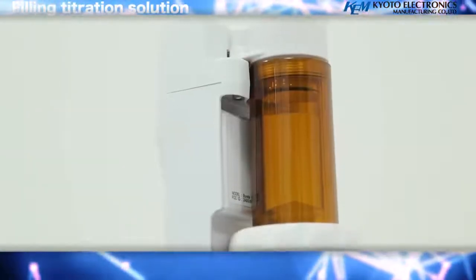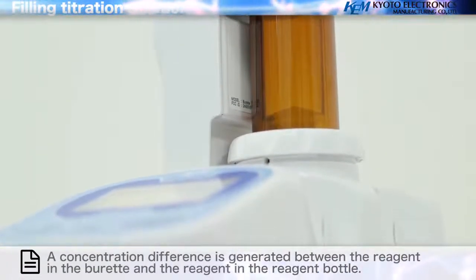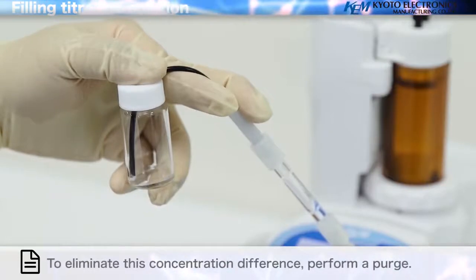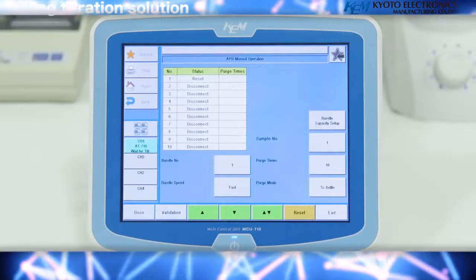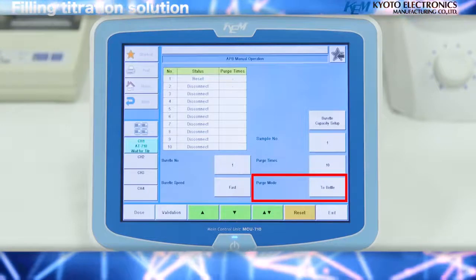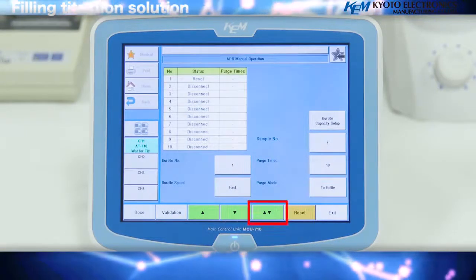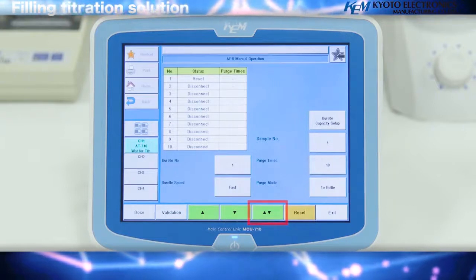Filling titration solution: a concentration difference is generated between the reagent in the burette and the reagent in the reagent bottle. To eliminate this concentration difference, perform a purge. Select the burette on the screen, select purge mode, select to bottle. Set the number of times to purge to 10, and press the up and down arrow keys to activate the piston 10 times to fill the burette while expelling excess air.